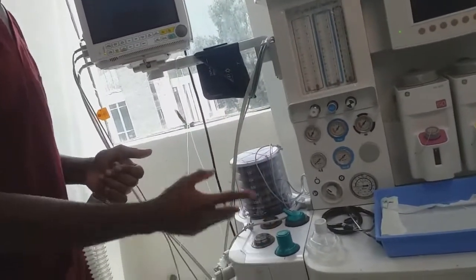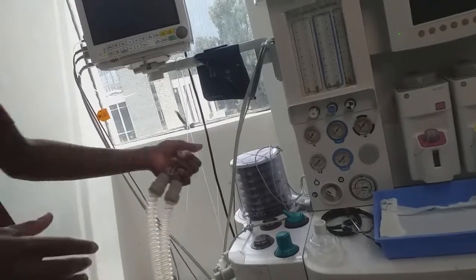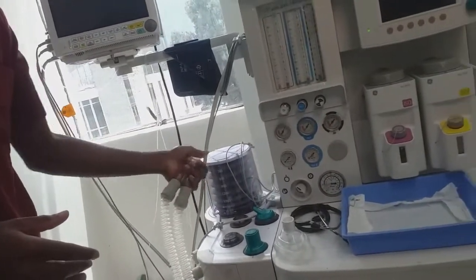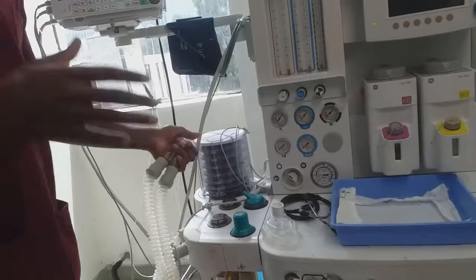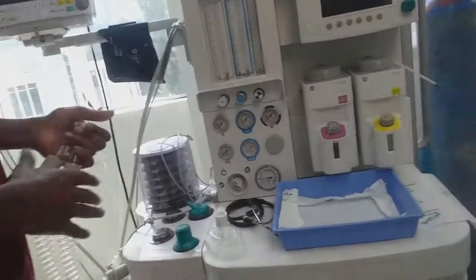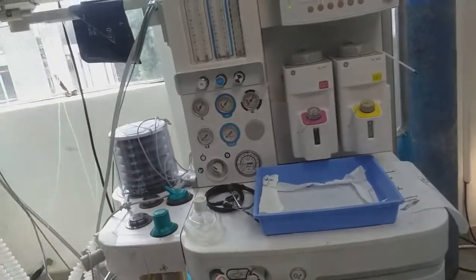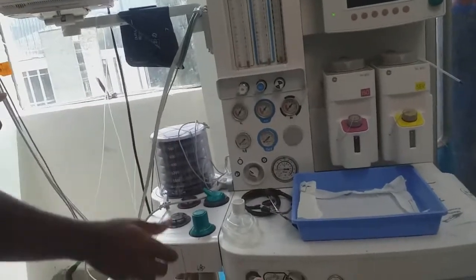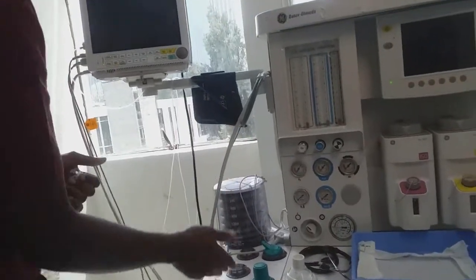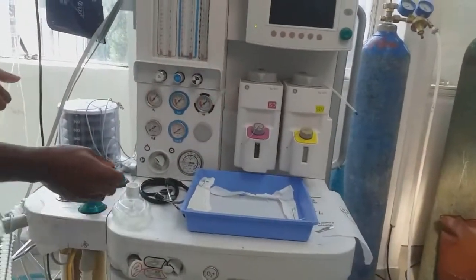The bellows fall should be less than 100 milliliters per minute. This indicates that there is no pressure leak, there is no mechanical ventilator leak. I have already checked. There is no leak on this ventilator. Okay.